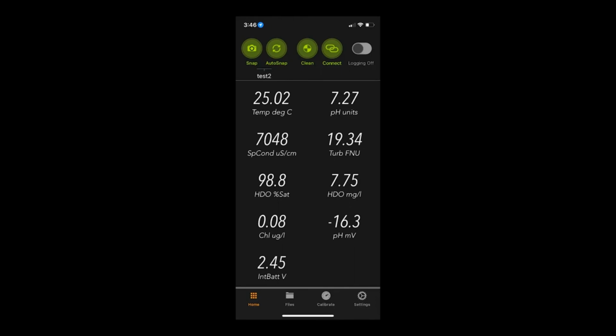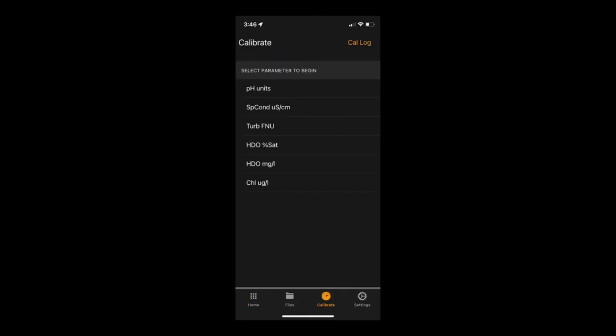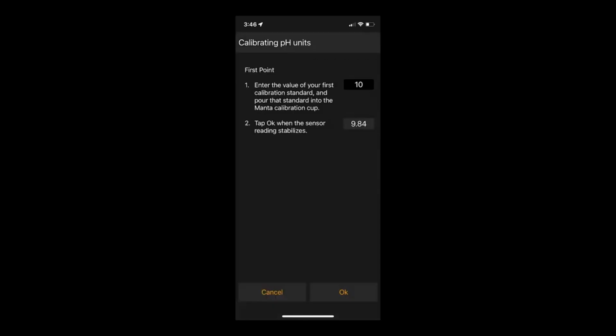Tap the MantaLink icon on your smartphone or tablet. Tap Connect at the top of your screen to connect to the MantaMobile device that corresponds with the serial number on your MantaMobile. Once connected, at the bottom of your screen, tap Calibrate. This will bring up a list of parameters to choose from to calibrate. Tap pH units, and then follow the prompts on your screen.